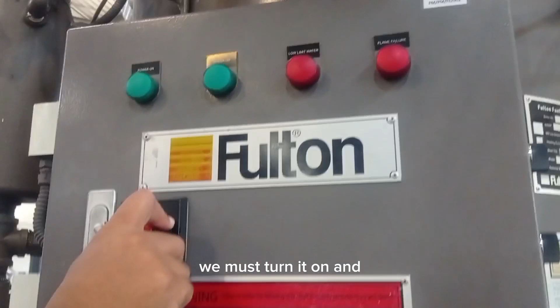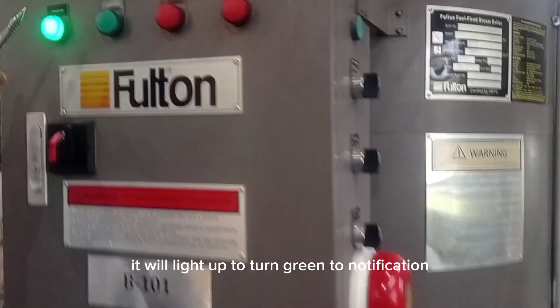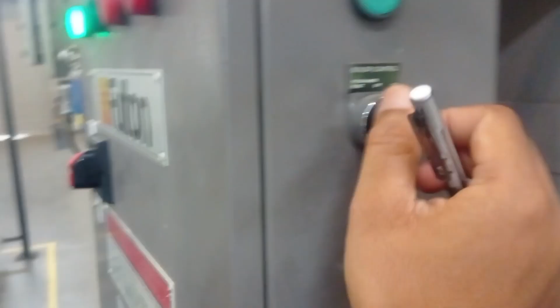After everything has been monitored, we can turn on the boiler. Turn on the electrical supply first, which is here, the switch. We must turn it on and it will light up green as a notification that it is ready to use. Next, turn on the boiler control, then turn the pump control to auto mode, and the blower control to auto mode also, and then let it run around 20 to 30 minutes. We can also monitor the increasing pressure at the gauge, so when the steam is ready, we can close V1.